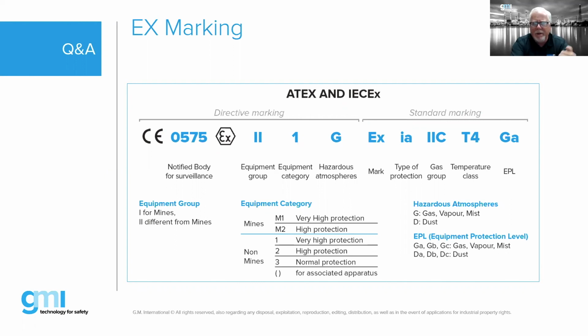So, for example, the pressure equipment directive or the low voltage directive or the EMC directive, they're all going to have CE marks, but they're not necessarily going to have that EX. So when you have a CE and the EX in a hexagon, that's telling you in effect that the product is compliant to the ATEX directive. The 0575 is a number that's unique to every notified body. Whoever your notified body is will have a 4-digit number, and it's the same 4-digit number for that notified body, whatever product, whatever manufacturer they get involved with. Then we get into our equipment group, which reflects surface industries. Anything above ground is going to be Roman numeral 2. Equipment category, in this case, could be 1, 2, or 3.